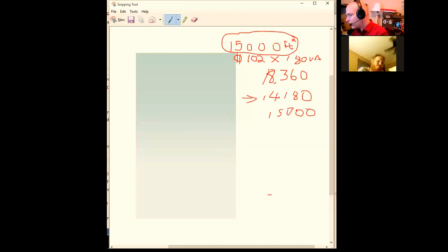Page 538. And I just put next to the note I there in the margins. Okay. Yeah. And then the D rate's just based on the number of receptacles you have there. It's just one number against the whole mass, but it's still going to be 180 VA per yoke, so you still have the same calculation there. 180 VA each, and the D rate conductor. 555.12.